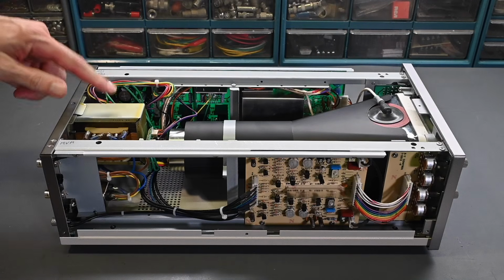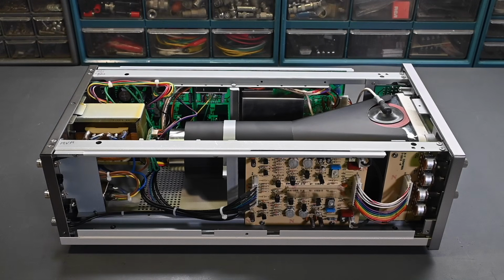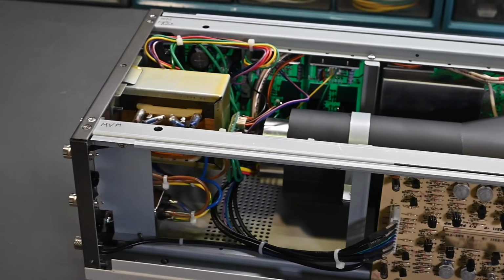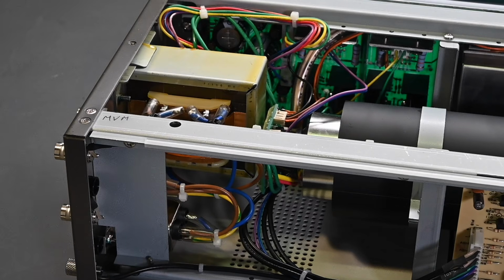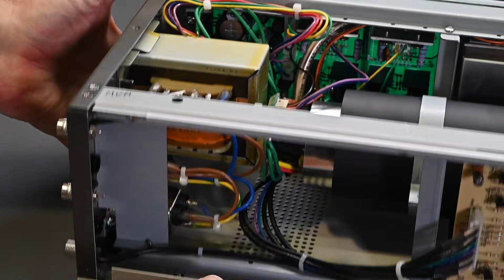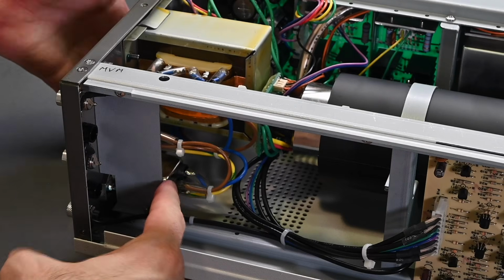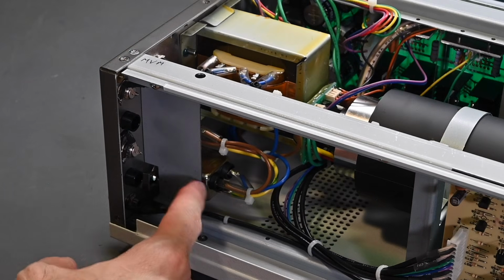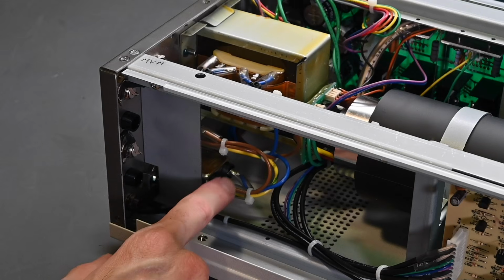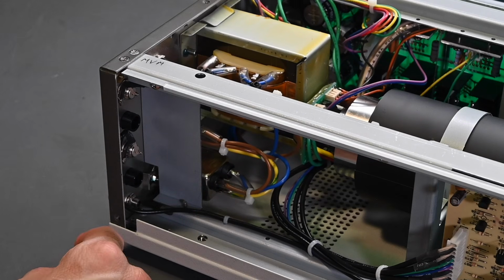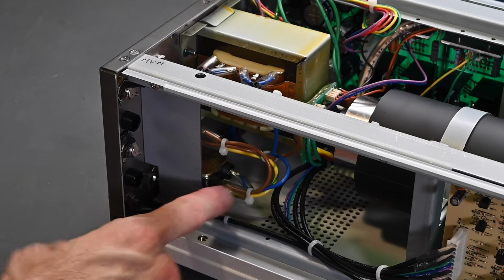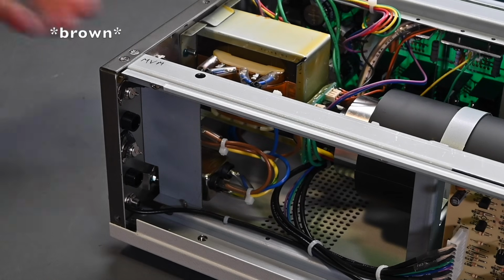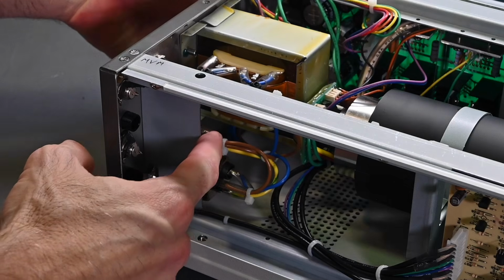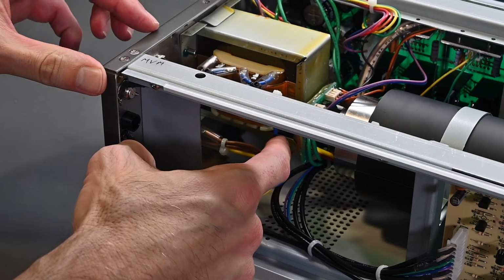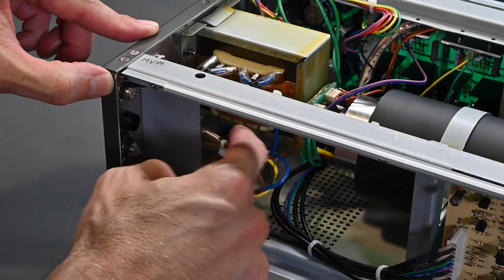So, transformer, so traditional linear type power supplies in here, not a switch mode supply. So it looks like down here there's an AC line filter, AC power connector, and then there's a blue, brown, and green wire. So the green is the chassis ground, blue is going to be neutral, and the brown is the hot. So the brown wire is going over to the fuse holder, and then off of the fuse holder it comes over here. Let's see, it's going up.